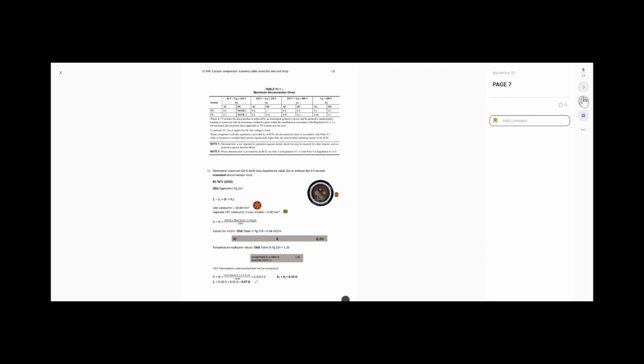So table 41.1, our nominal voltage is between 120 and 230, so I'm using the second column in. It's on a TN system, it's AC. So therefore our maximum disconnection time is 0.4 seconds. So this type C 32 amp breaker has got to disconnect in the maximum time of 0.4 of a second. So just under half a second, we've got to make sure that's what happens. Okay, last week it was 5 seconds, but this week, super quick this week, 0.4 seconds. We've got to make sure that happens.